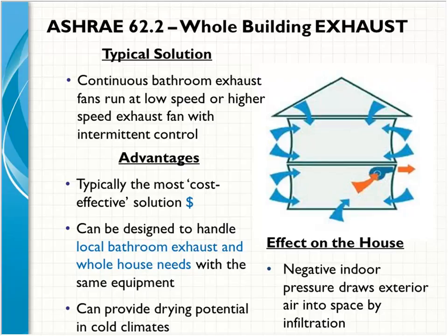So as I mentioned before, exhaust ventilation is simply using an exhaust fan, often placed in the bathroom, to meet our ventilation requirements. We've been using bath fans for many years. To use them as a whole house ventilation system really means just upgrading to a better bath fan that runs quieter, is rated to run continuously, and does its job, hopefully unnoticed, relying on the building shell for the makeup air, if you will, or the fresh air. Again, this is the most cost-effective means to meeting your requirement, because you're just buying a little bit better bath fan and using that, doing your calculations, and then programming that fan to run automatically without homeowner or occupant interaction to meet the code.